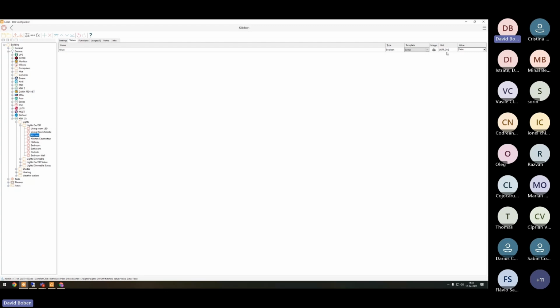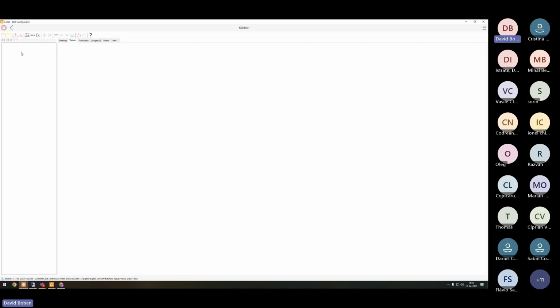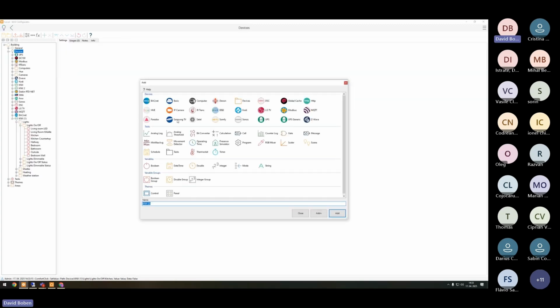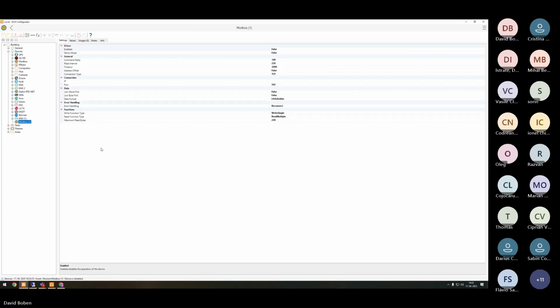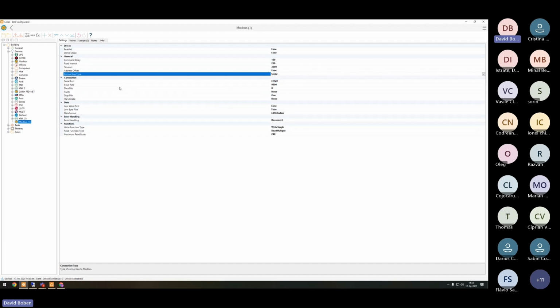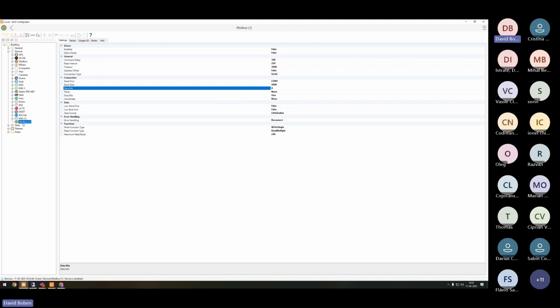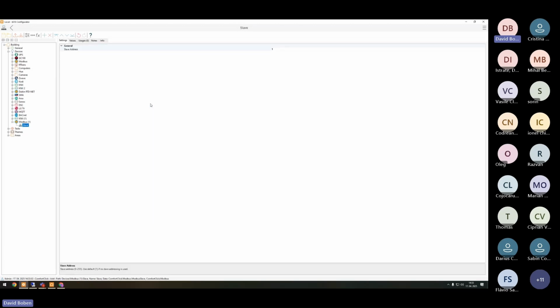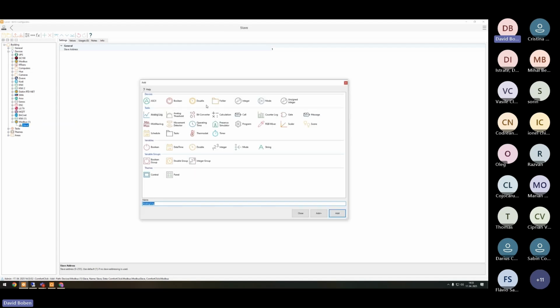Very similar process is for other devices. Let's say if you have a Modbus device, for instance, you would go to Modbus here, add it in. When it comes to Modbus, having a manual of the device is crucial. So here, the manual is going to contain all the connection settings, all the address settings, and so on. So if I have an AC unit, the connection type is serial connection, so I will switch the connection type. The manual will contain what is the baud rate, parity, data bits, and so on. The manual will also contain what is the slave address, and then the manual will also contain what addresses I can use to control my Modbus device.